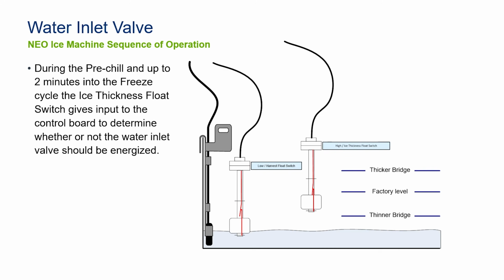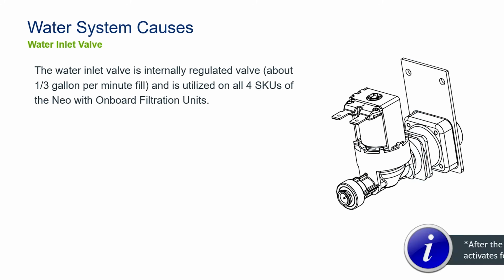So the water inlet valve, we're going to talk about how a water inlet valve can cause a service limit number 1 long freeze. Keep in mind, a lack of water is not that reason. This ice machine has a service limit 3 or water loss safety, so a lack of water is not going to have this happen. So what are we looking for? How does the water inlet valve operate? During pre-chill and up to 2 minutes into your freeze cycle, we're going to utilize the ice thickness float switch to bring in water until we fill to the factory level.